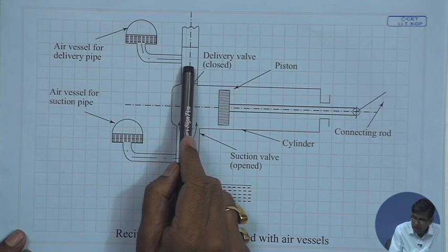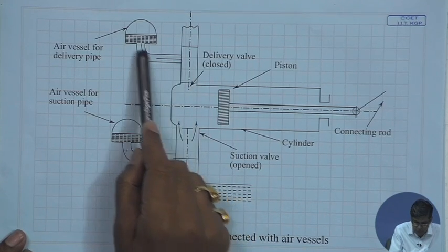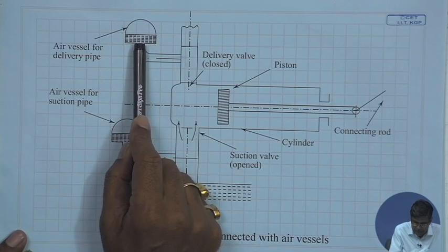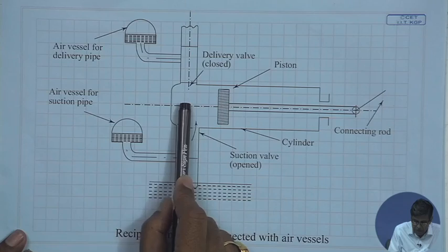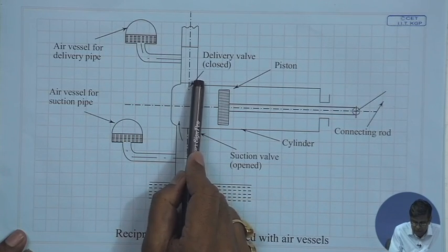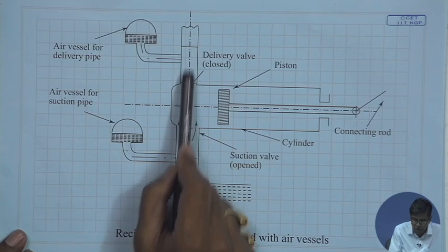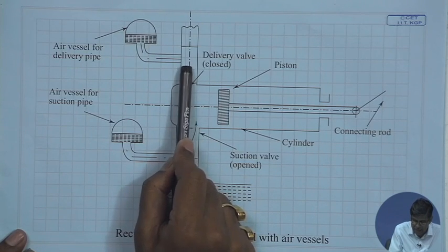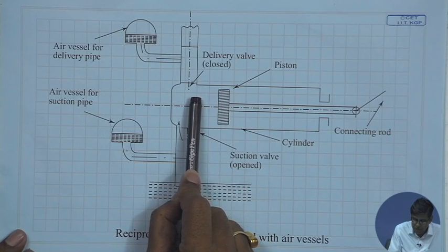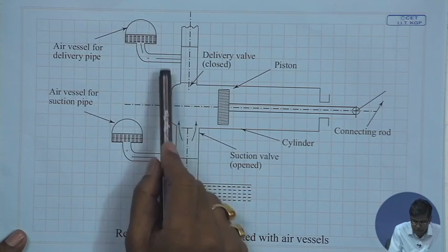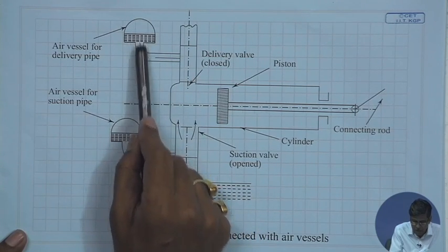So, additional discharge goes here in the initial part, and where the discharge rate is less at the end of the delivery stroke, the water comes through this. So, therefore, in this part of the pipe, the discharge is fluctuating more at the initial part in consideration of the acceleration rate and less at the latter part of the delivery stroke in consideration of its deceleration. But in both the parts, this acts to absorb and release water.